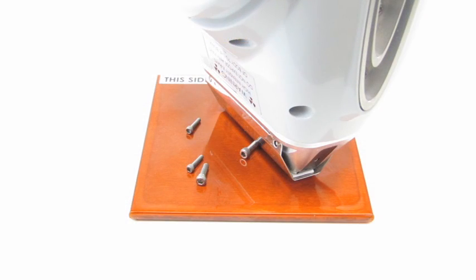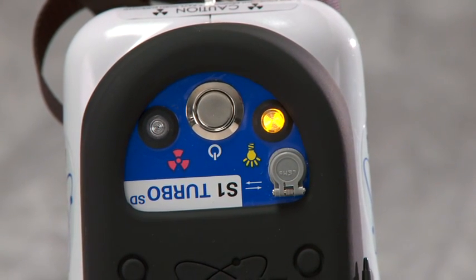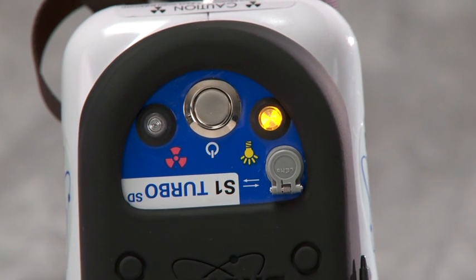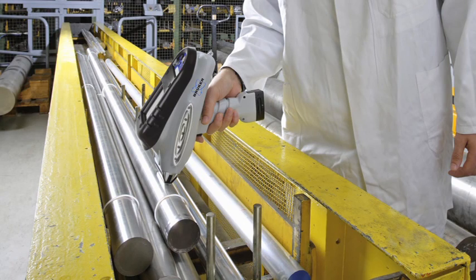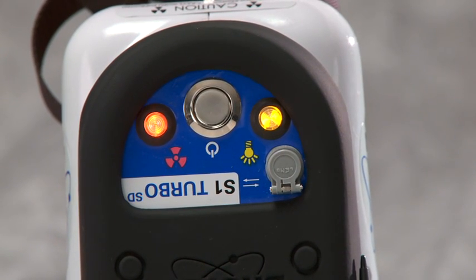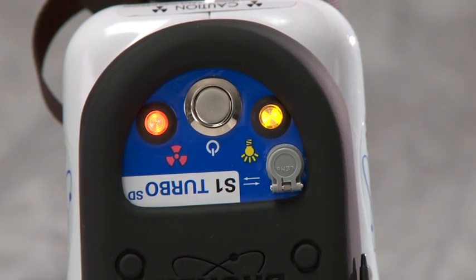If the sample does not cover the IR sensor, the safety circuit will not allow X-rays to be generated. The red light on the control panel will not illuminate, and no measurements can be made. Once the IR sensor is satisfied and the trigger is activated, the red light on the control panel will illuminate and the measurement will begin.